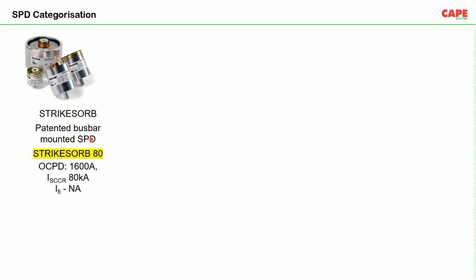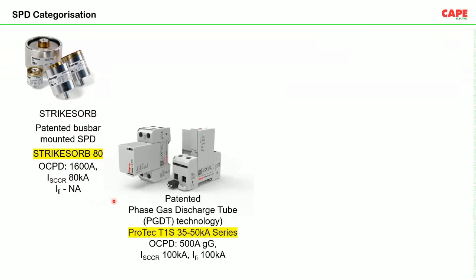It's a bus bar mounted SPD, which has a lot of advantages, which I will show in the next slides. For example, one of the models, StrikeSorb 80. OCPD means overcurrent protective device. When you connect it to a line, it requires a backup protection, and the backup protection can be up to 1600 amps ACB, for example. The short circuit current is 80 kiloampere. The nominal discharge current is here, follow current IFI is not applicable. That is, I'm just showing some of the parameters of this particular device.